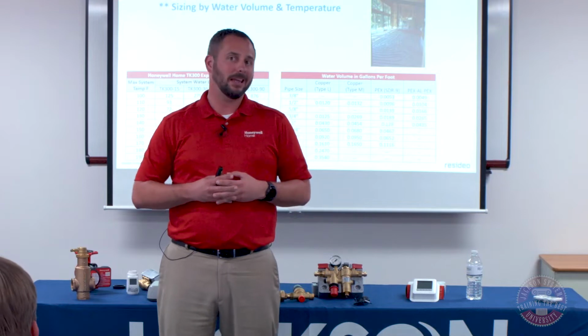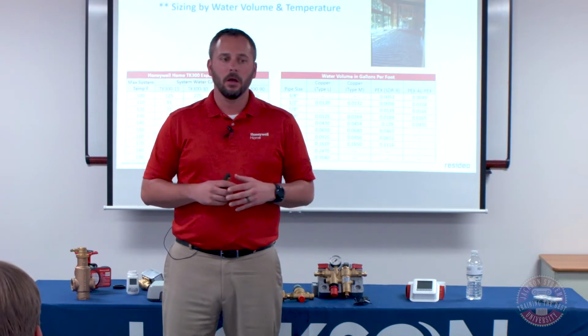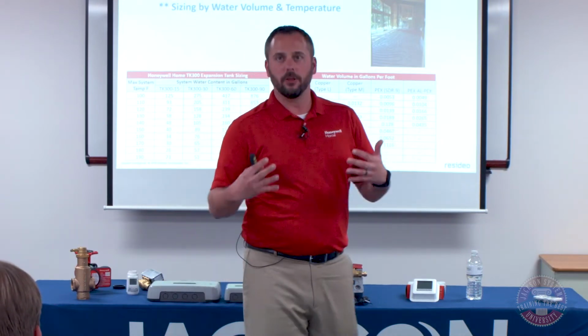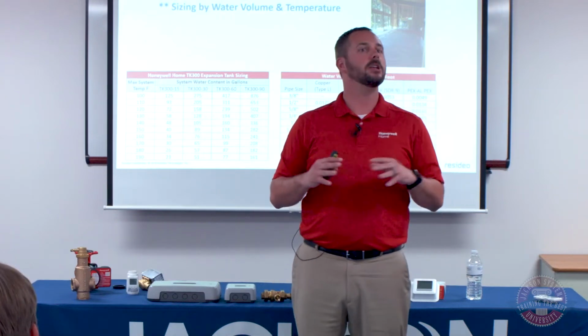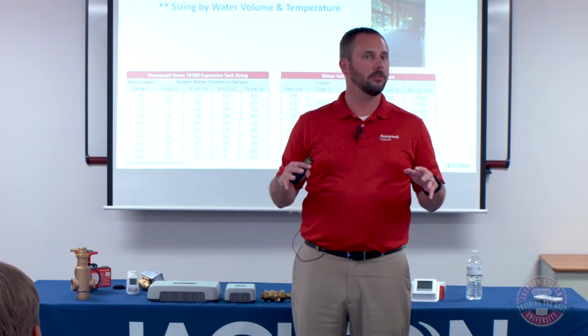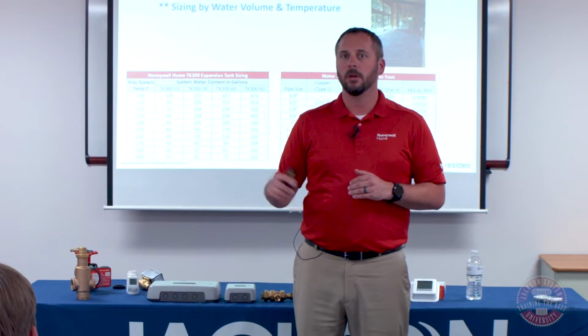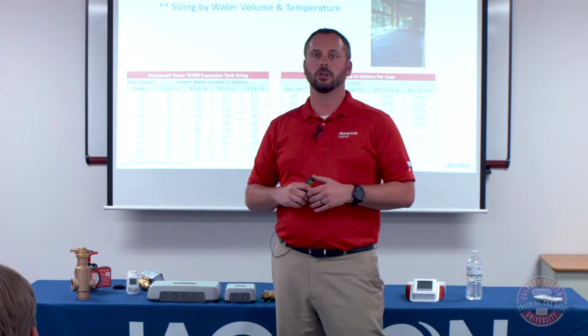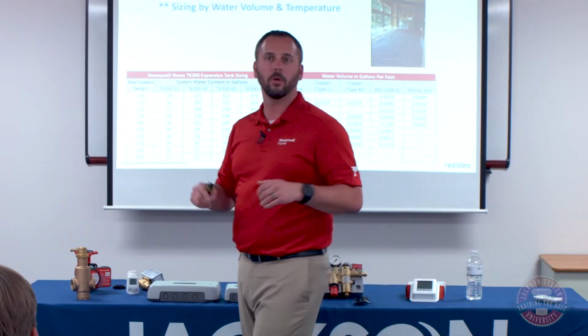You don't have to be incredibly exacting, because my mantra on expansion tanks is if you're anywhere near the maximum capacity, go to the next size up. Expansion tanks don't hurt going larger in size. So if there's any question, always go larger.